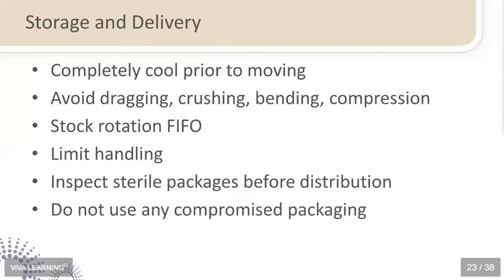Storage and delivery. When instruments come out of your sterilizer, before you move them or transport them to where they're going to be stored, they should be completely cool. You should not be putting warm instruments into a transport container, because while the pack is still warm, the fibers of the material are more vulnerable and you could get tearing, ripping, puncturing. So make sure that it's totally cool, that there's no moisture, and that you're not doing things like dragging them across the countertop.